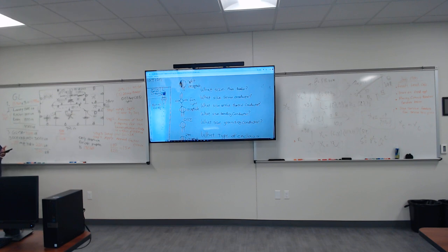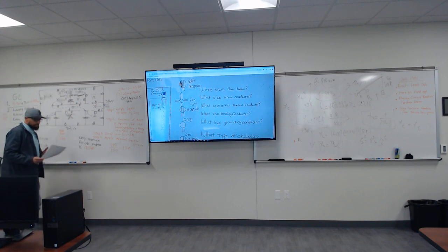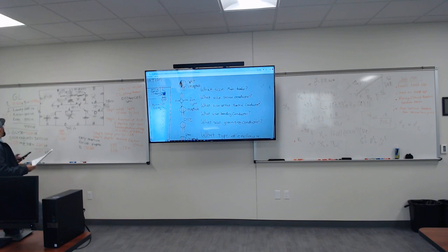All right, I'm going to add number 1, 2, 3 all the way down to number 7. For number 1, I have 4,788, plus number 2 is 4,500, plus number 3, the demand factor, 5,201, plus number four, 7,734, plus the dryer, 5,000, plus the cooking unit is 8K, plus the heating unit, 15K.